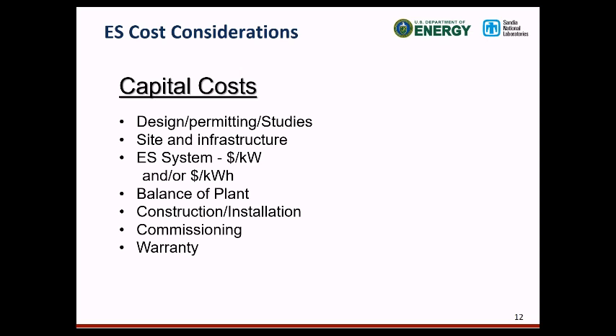Then you have your energy storage system cost, dollars per kilowatt, dollars per kilowatt hour. One thing I didn't mention, back in your programming stage you need to be thinking about what size you really need and what energy capacity you need to get the most bang for the buck. You also have your balance of plant — any air conditioning, fire suppression, lighting, etc. Then you have your construction and installation cost, your commissioning cost, which a lot of times is not really known until it's too late, because you want to do a detailed commissioning of the system so you know it's going to be safe when you start it up and run it.